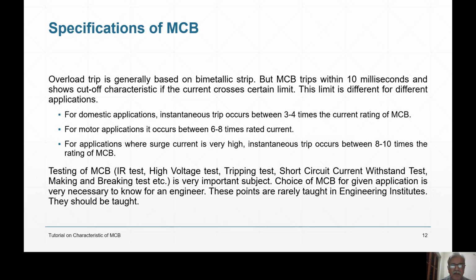You have to test the MCB, tests like the IR test, that is the insulation resistance test, which you do by Megger, and the high voltage test. What is the method of this testing? That is written in the IS. And if you do these tests one by one, you will understand how much time you take for an MCB. For one MCB, practically you will take at least 2 or 3 days to learn. High voltage test means both the terminals you have to short. Between both the terminals and the earth, you have to apply 2.5 kV, 2500 volts, and the insulation should not be damaged. 2500 volts only for 1 minute.